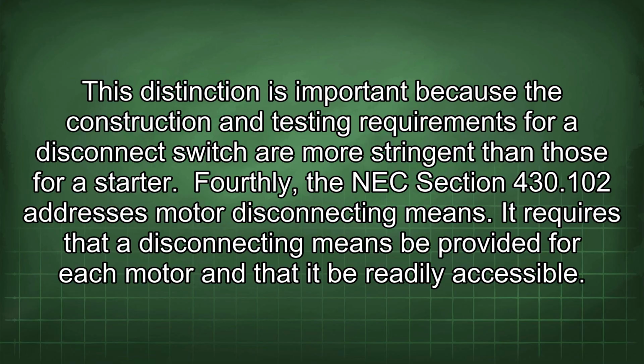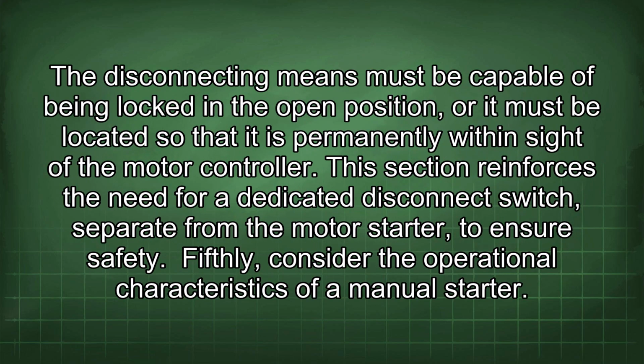430.102 addresses motor disconnecting means. It requires that a disconnecting means be provided for each motor and that it be readily accessible. The disconnecting means must be capable of being locked in the open position, or it must be located so that it is permanently within sight of the motor controller. This section reinforces the need for a dedicated disconnect switch, separate from the motor starter, to ensure safety.